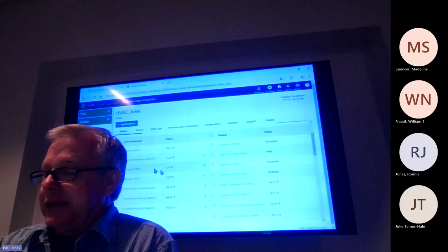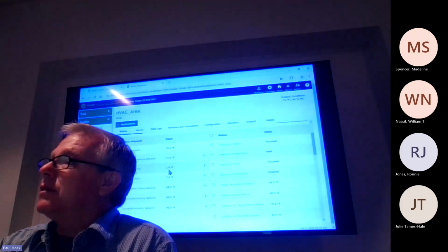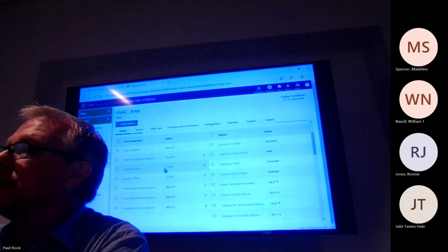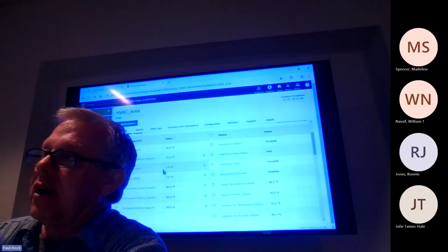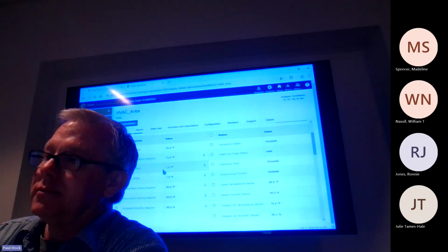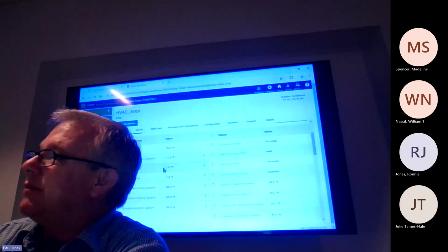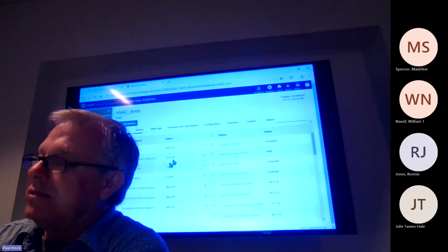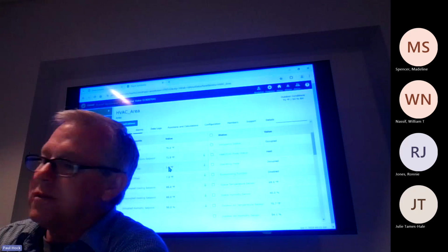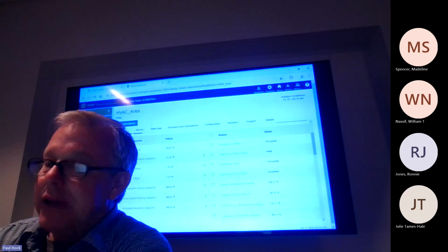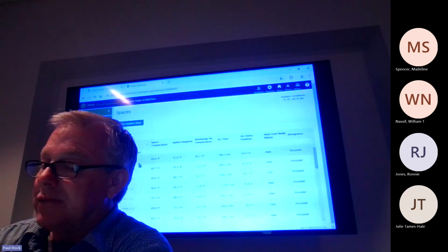And then on your spaces, you'll see this 1 degree offset. That's going to be 1 degree above and below your set points. So your active set points are going to change based on that offset. That's like the acceptable range. Yeah, we're trying to keep it 70 to 72. And you will be able to change those.